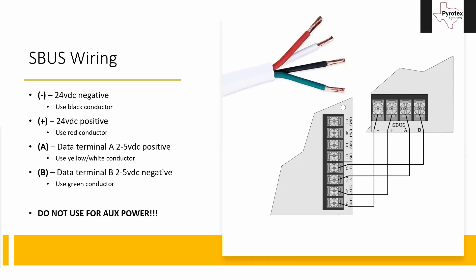Going back to the meter: black lead to negative, red lead to positive — you should see about 24 volts across those two terminals. Then move your leads and put the red on A and black on B. You should see somewhere between two and five volts DC. It varies depending on how many devices are on the circuit, but as long as it's above two volts, you've got enough signal strength. If it dips below two volts, that's when we use the RPS 1000 or the 5895 power supplies, which have an SBUS repeater built in.